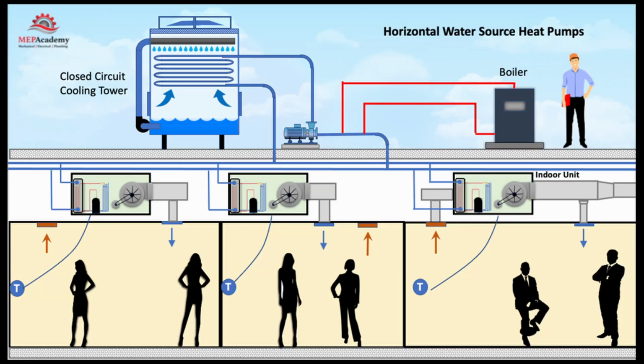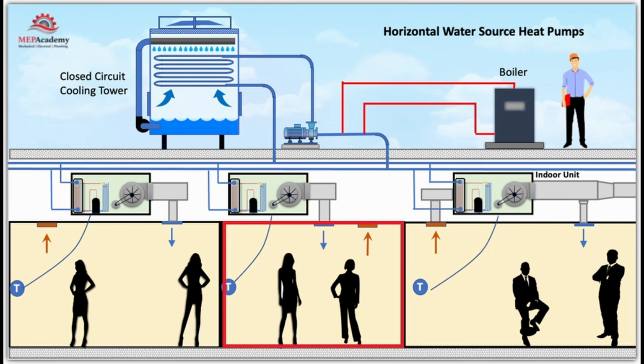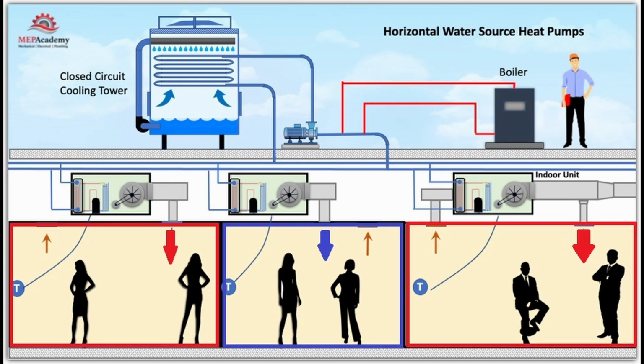We have already covered where an air-to-air heat pump rejects its heat. So now let's look at where a water source heat pump absorbs and rejects its heat. One of the coils is exposed to a water loop, and the other coil is exposed to the air that circulates through the occupied space. The water loop travels to each of the water source heat pump units all throughout the building. In swing season, where rooms on the exterior of the building may need heating in the morning, and rooms on the interior of the building may need cooling, the heat from the interior will be rejected into the water loop and can be absorbed by the units serving the exterior of the building, making the water source heat pump system more efficient than the air-to-air heat pump.